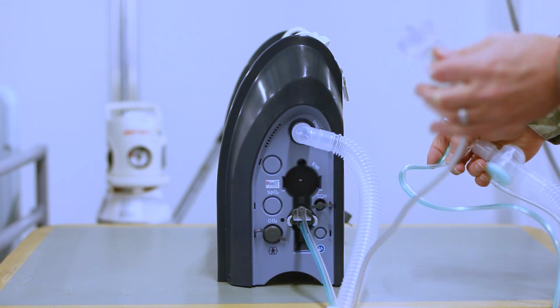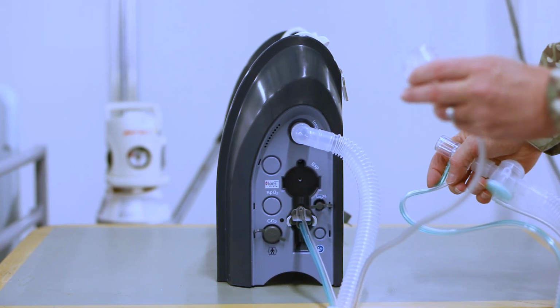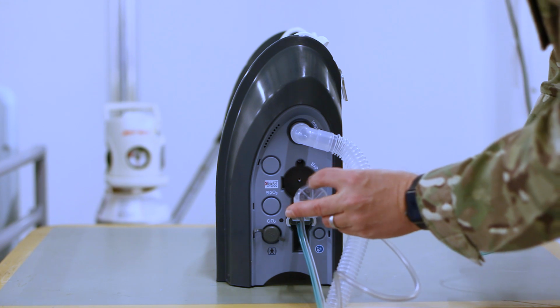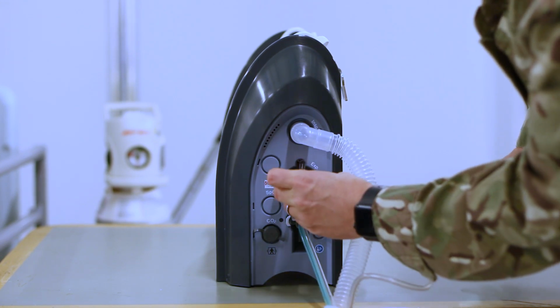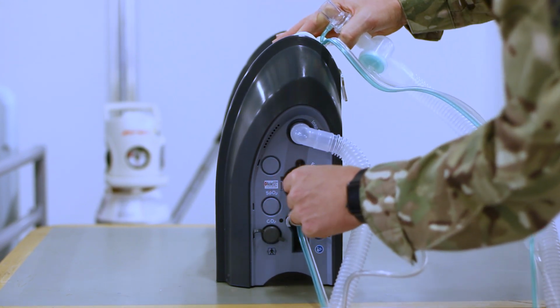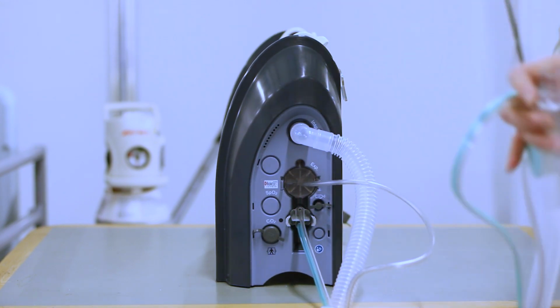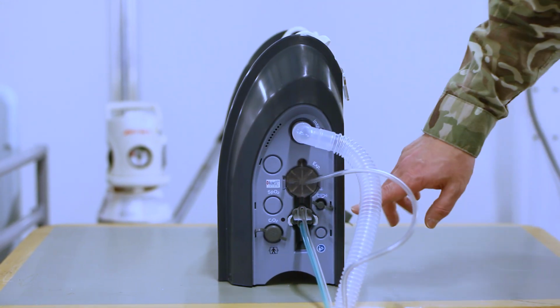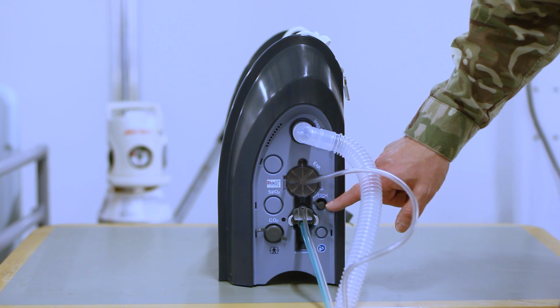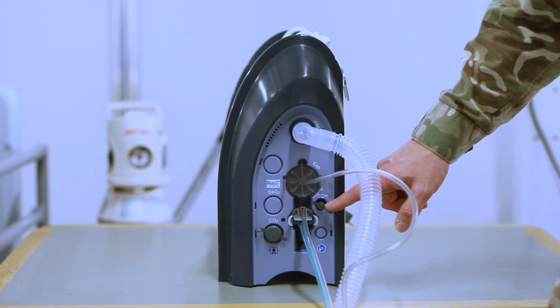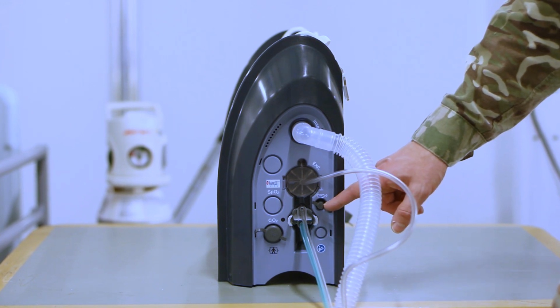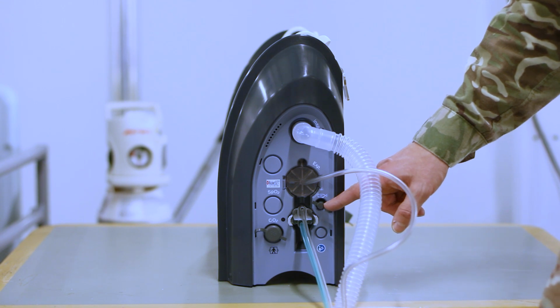And then on the expiratory sensor, which may come in slightly different ways, this will have a notch which matches the notch of the expiratory side, and that will clip in there. It will only fit one way. Just to the side here, there is also a nebulizer function which allows you to nebulize in a circuit if attached to high pressure oxygen.